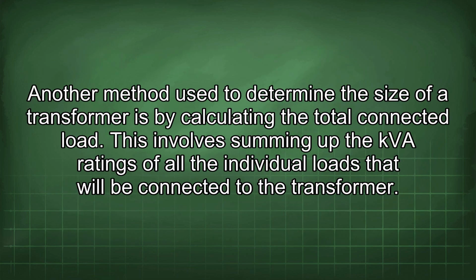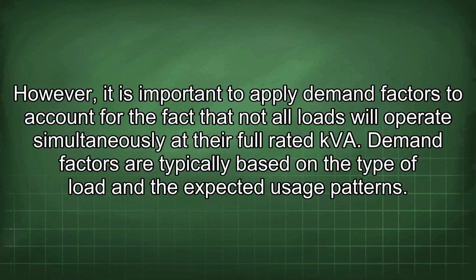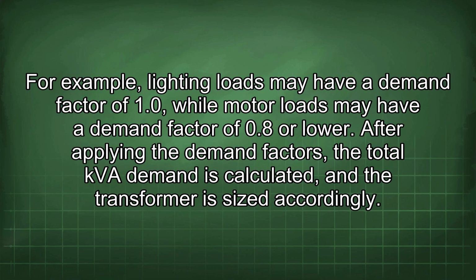Another method used to determine the size of a transformer is by calculating the total connected load. This involves summing up the kVA ratings of all the individual loads that will be connected to the transformer. However, it is important to apply demand factors to account for the fact that not all loads will operate simultaneously at their full rated kVA. Demand factors are typically based on the type of load and the expected usage patterns. For example, lighting loads may have a demand factor of 1.0, while motor loads may have a demand factor of 0.8 or lower. After applying the demand factors, the total kVA demand is calculated, and the transformer is sized accordingly.